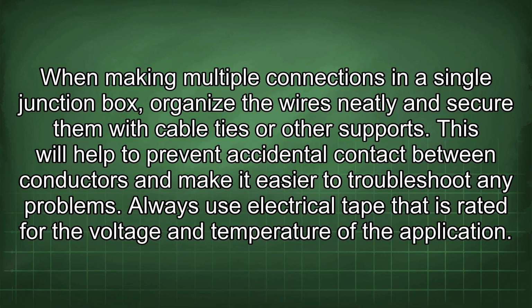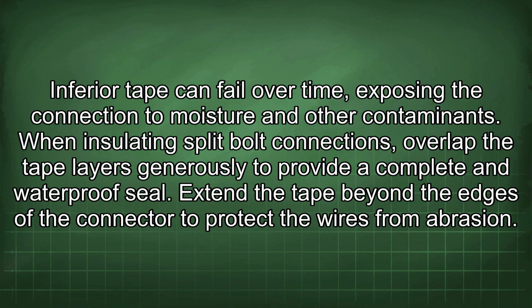Always use electrical tape that is rated for the voltage and temperature of the application. Inferior tape can fail over time, exposing the connection to moisture and other contaminants. When insulating split bolt connections, overlap the tape layers generously to provide a complete and waterproof seal. Extend the tape beyond the edges of the connector to protect the wires from abrasion.